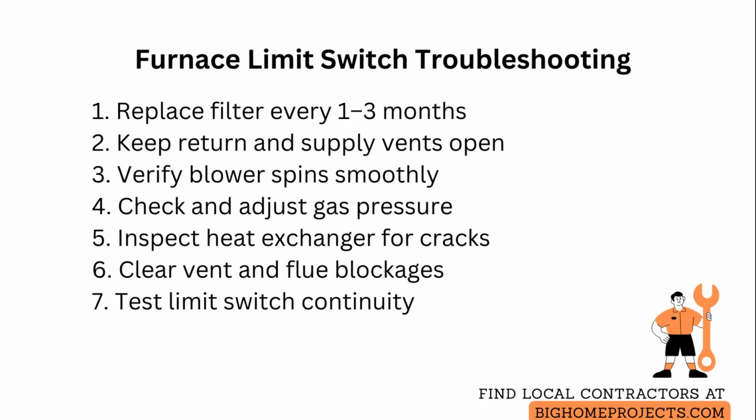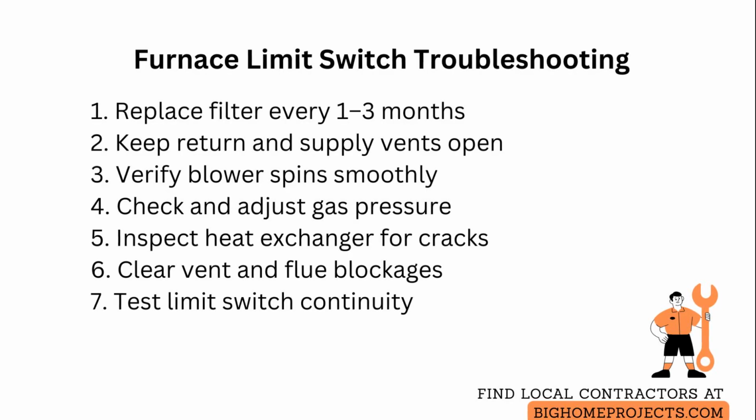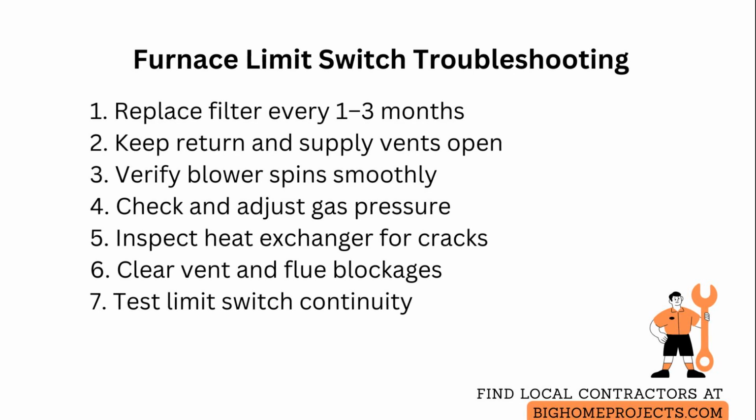Inspect return and supply vents to ensure they are open and unobstructed, and confirm the blower wheel spins freely by turning the fan on separately and listening for smooth operation. A failing blower motor or loose belt will reduce airflow and create heat buildup.